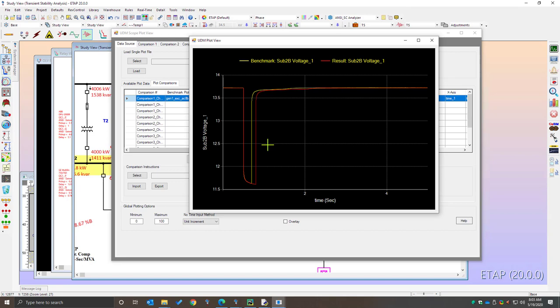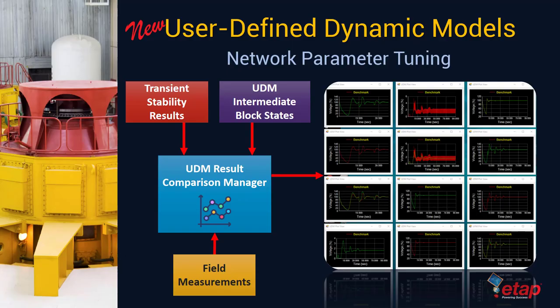Here we are comparing the output of transient stability along with measurements made at the terminal of the machine, so this tool can be used quite effectively in response evaluation, plot comparison, and obviously for network parameter tuning. You can perform unlimited plot overlays and comparisons, and produce results along with the benchmark file for grid code compliance for operational systems. In summary, network parameter tuning can be done through taking UDM intermediate block states, transient stability results, and field measurements compared together, and this information can be used to not only tune your network model but also produce a deliverable for operational grid code compliance.